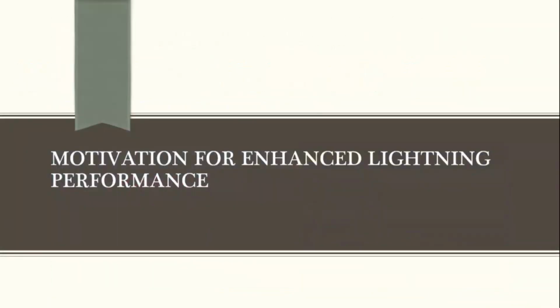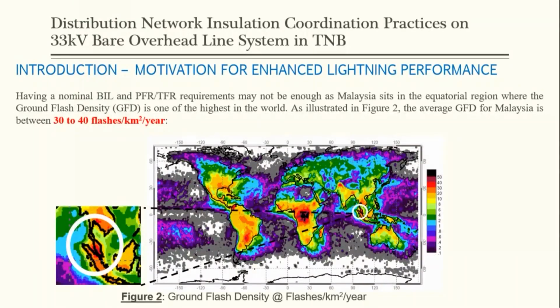Okay, so what is the motivation for having an enhanced lightning performance? Why do we care a lot about our installation, right? In Malaysia, for example, we don't have any choice, right? Having a nominal BIL and PFR or TFR requirements may not be enough, as Malaysia sits in the equatorial region where the ground flash density, or GFD, is one of the highest in the world. As illustrated in figure 2, the average GFD in Malaysia is between 30 to 40 flashes per kilometer squared per year. It's one of the highest in the world, okay? So we have no choice. We have to do a lot to protect our medium voltage overhead lines.